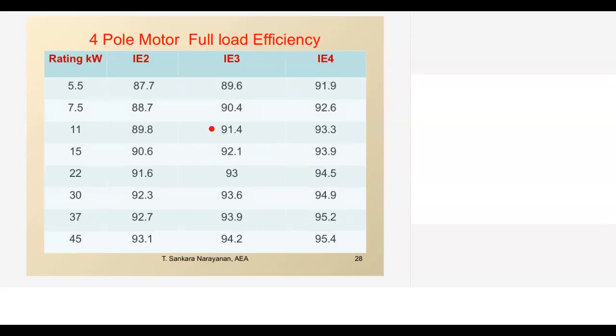This is a case for full load efficiency of different motors, IE2, IE3 and IE4. Now if we see for different ratings, this is given from 5.5 kilowatt to 45 kilowatt. At the lower range, the efficiency margin between IE2 and IE3 is around 2%. Let us take IE4 afterwards. When we go to a higher range, the efficiency margin between IE2 and IE3 is less. So one always has to review which motors we should go for replacement. Motors which are running for a longer period are all good cases for replacement.